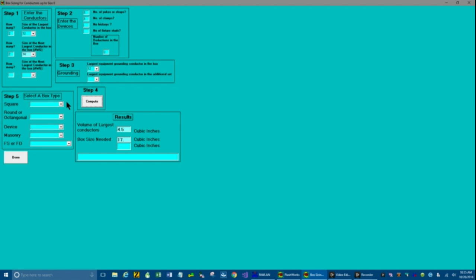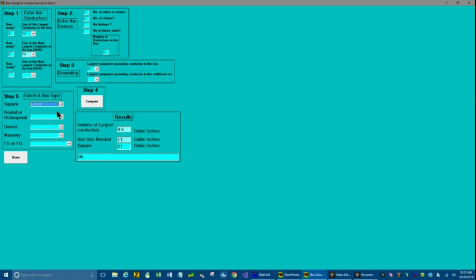Go over to box in step 5, box, and go to square boxes. And you see there's a list of square boxes. So let's just try a 4 by 1.5 inch box. It says that size is 21 cubic inches. And notice it says you could use that box.